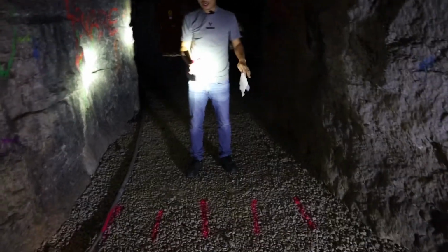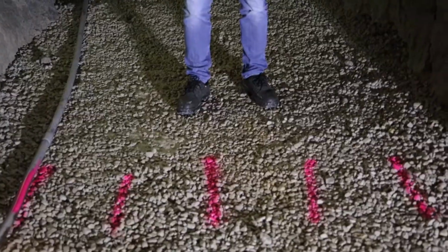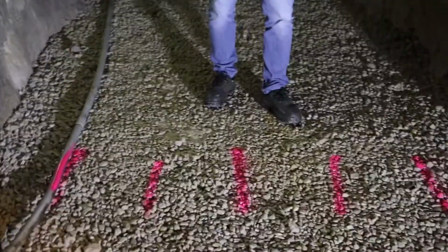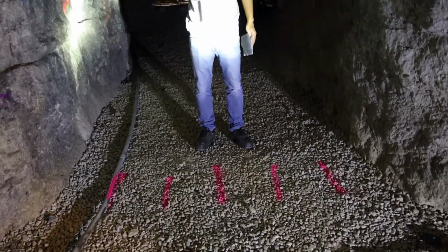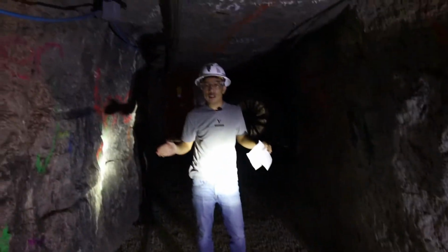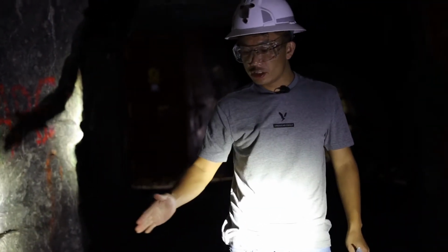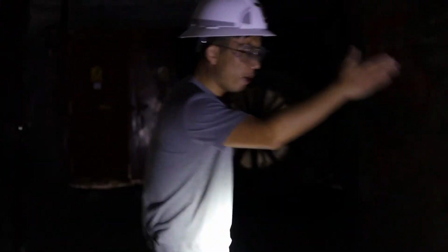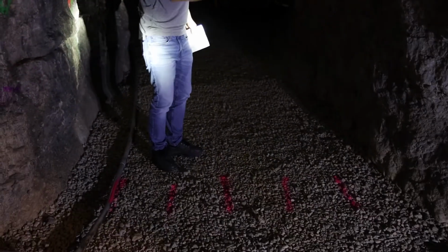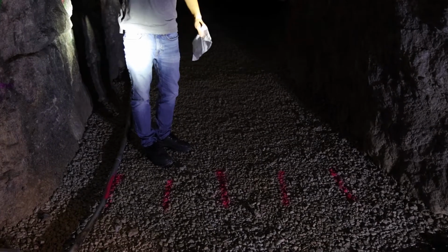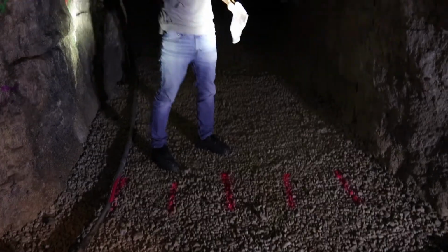This will roughly divide the airway into about 6 sections. I will use these lines to guide my path of the traverse. If you have a wider airway, you will need to have more of these lines because you want to have more passes so that you can cover the entire cross-sectional area of this airway.